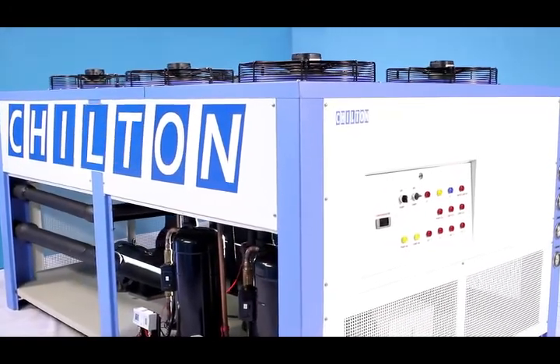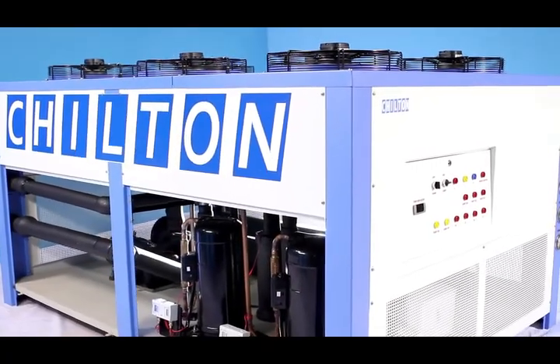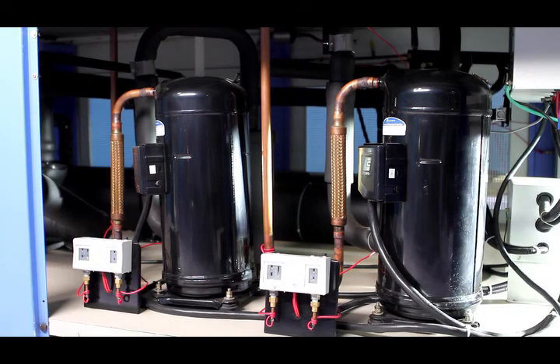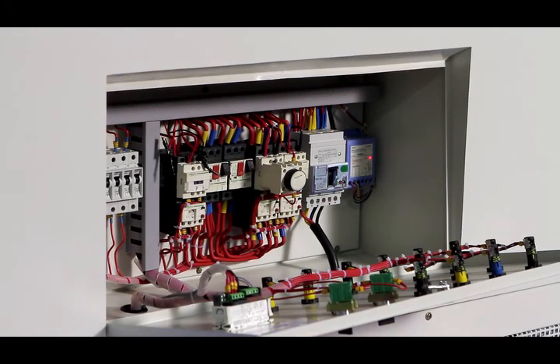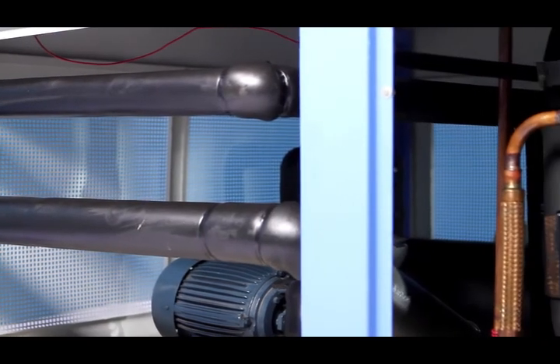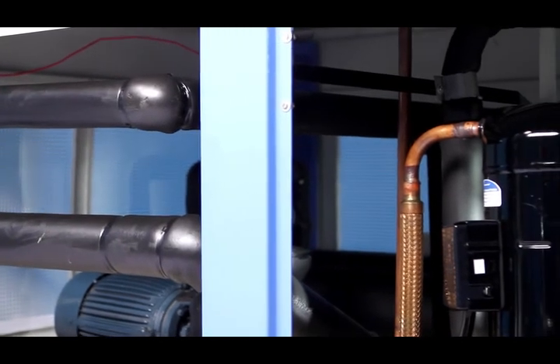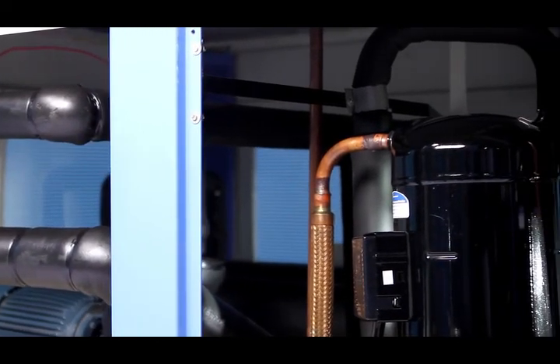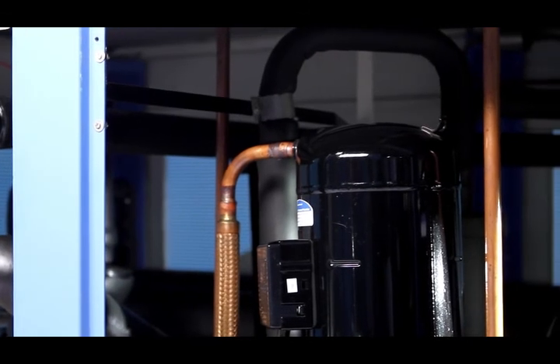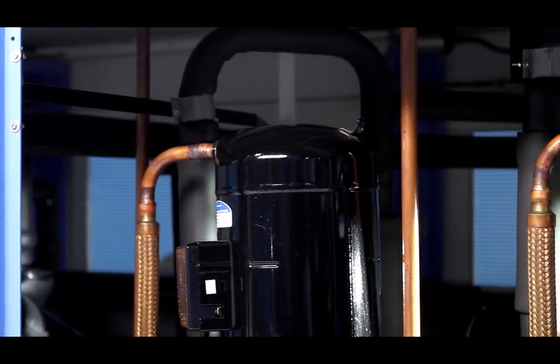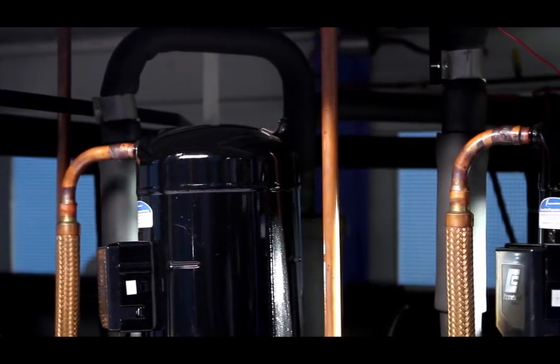Maintenance. The machine is designed in such a way that you can remove the side covers and run the unit simultaneously to do the maintenance work physically by seeing the functioning of each component. Even routine maintenance work of cleaning the condenser can be done without switching off the chiller. This makes maintenance work more simple and easy.